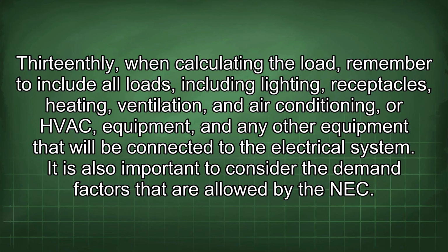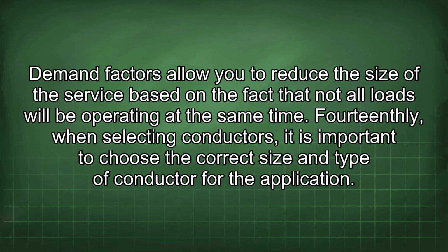13thly, when calculating the load, remember to include all loads, including lighting, receptacles, heating, ventilation, and air conditioning, or HVAC, equipment, and any other equipment that will be connected to the electrical system. It is also important to consider the demand factors that are allowed by the NEC. Demand factors allow you to reduce the size of the service based on the fact that not all loads will be operating at the same time.